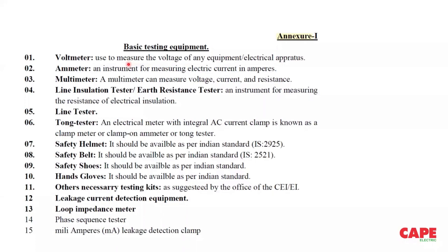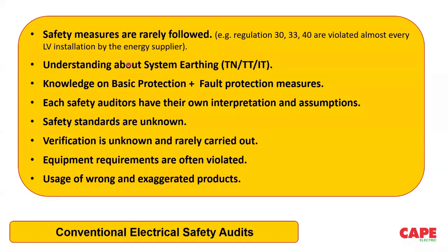Probably you can make an audit, because audit is only partial. Verification is not possible. Why I show these tables is that there is one more regulation which I will refer to a little bit later so that you will be able to understand the importance. So basically the problems are, safety measures are rarely followed. For example, regulations 30, 33, 40 are violated in almost all low voltage electrical installations. Guarding is not there. The protective regulations 14, 15, 16, the earthed conductor from the supplier side, is not available in most of the state governments. So these are actually attributing to the large number of accidents.